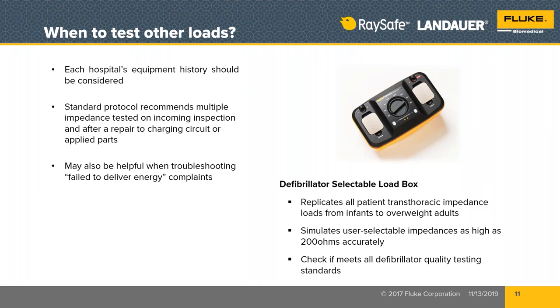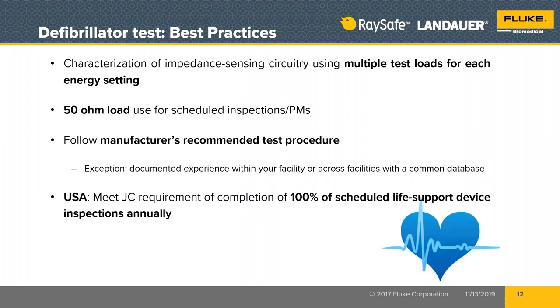How about after repair? Sometimes if you're not doing the repair in-house, it's going out and coming back in. So that's another instance of the acceptance test. But if you just did a repair, even if all you replaced was the battery, you need to retest. And again, I'm not talking about AED so much, but I'm really very much talking about full ACLS defibrillators. If you replace the battery or the capacitor or any part of the charging circuit, you need to repeat these tests to ensure that that functionality of the output energy guarantee is really still there, that you didn't interrupt it, that you didn't do something to prevent it from working properly. Okay, so we've already talked about this. I don't need to talk about it a lot more.